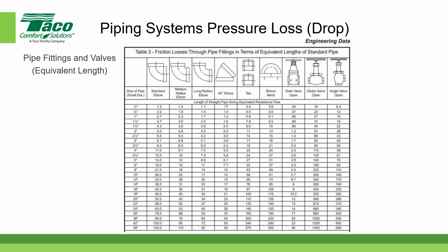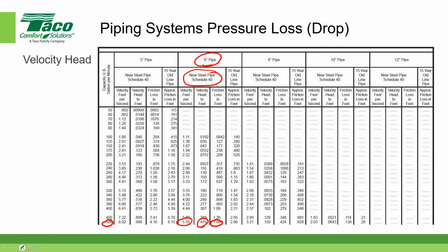Now, when we do an actual pressure drop calculation, we're going to use the equivalent length method. Let me go back one more time here. I'm going to erase these little dots so it doesn't become too confusing. I just said that the pressure drop in this pipe here at 500 gallons per minute, a 6-inch pipe, again, I'm circling some stuff here so we're all on the same page, in feet per 100 feet, in this case, is 1.66. So if I had a piece of pipe, this particular pipe is 6-inch diameter, and I was circulating 500 gallons per minute through this pipe, I would see a pressure drop over that 100-foot length of 1.66 feet. That's what that means, 1.66 feet.